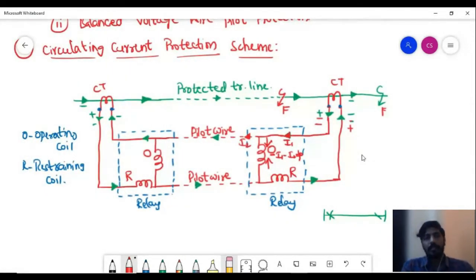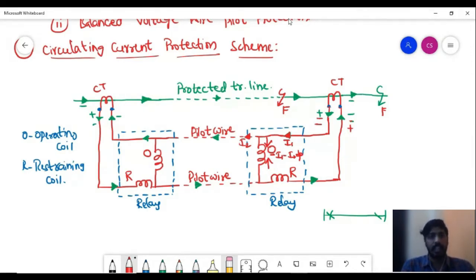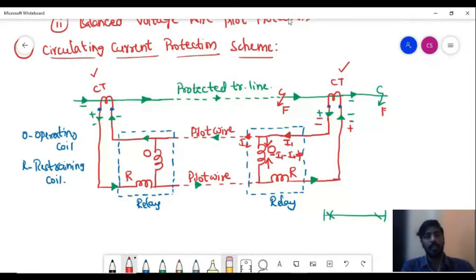This is a circulating current protection scheme — one type of pilot wire protection scheme. We have a transmission line; the green color line indicates the transmission line which we need to protect. In order to provide protection for this transmission line, we are going to connect CTs at the sending end and another CT at the receiving end. These are the CT secondaries.